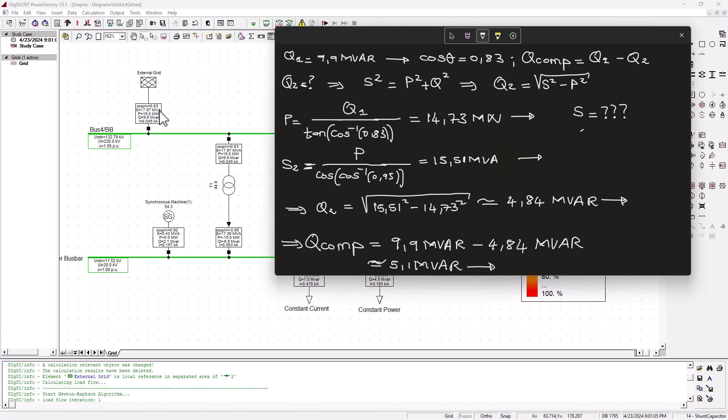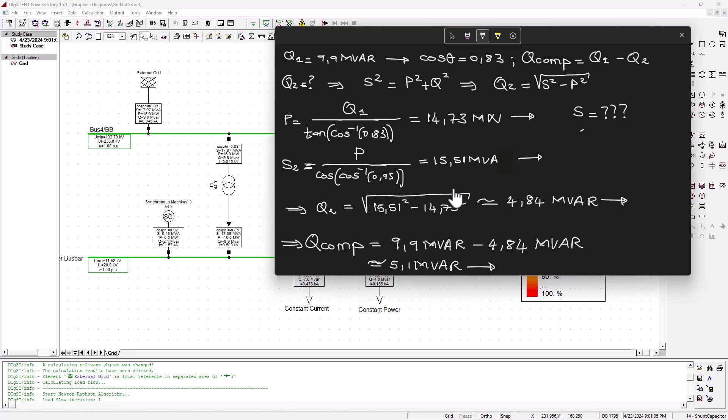But if we need to bring the power factor to 0.95, that means we need to find a new S, and that will ultimately give us a new Q. So this is what we are doing here. Then we say, well, the new S, S2, is then P divided by the new power factor, PF of 0.95.